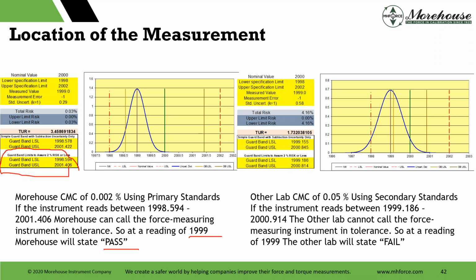Customer sends this to another laboratory. Their uncertainty is a bit higher than ours, right? They're using secondary standards that are 0.05%. And the instrument needs to read between 1999.186 and 2000.914. A lot shorter window. The other lab cannot call the force measuring instrument in tolerance at 1999 since it's not within this band, so they will have to either report the asterisk or they will have to report fail.